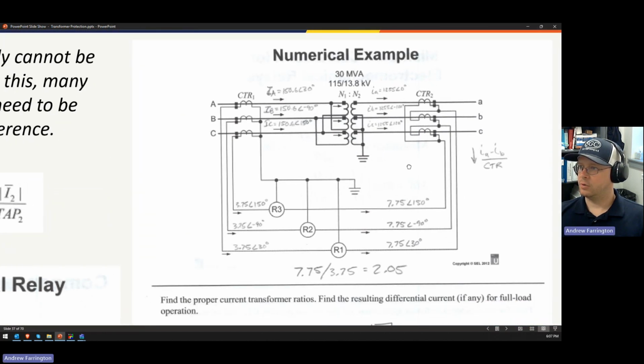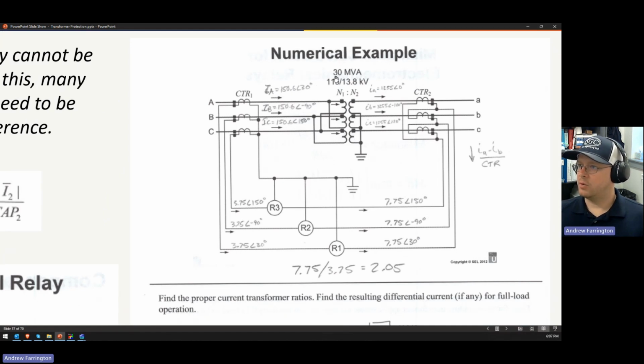So what I did is take the 30 MVA transformer rating and calculate what the phase current will be for that. And I included the angles here. I assumed that the low side current was at an angle of 0, and then I included all the angles here so that I can get the vector summation so that you can actually see that the current seen by the relay is actually in phase. So in practice, as long as you set up your CTs correctly here, you don't need to worry about that. But I thought it was good to include anyway.